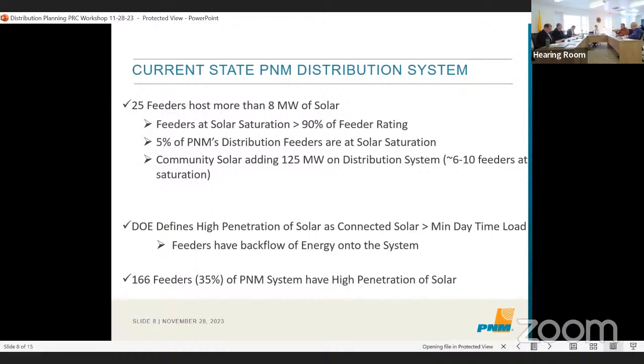The DOE defines high penetration of solar as solar penetration greater than the min daytime load, which really means you have reverse power on the distribution going back to the substation. If we look at the PNM system, roughly 35% of our feeders have more solar than daytime min load. That's 166 feeders.